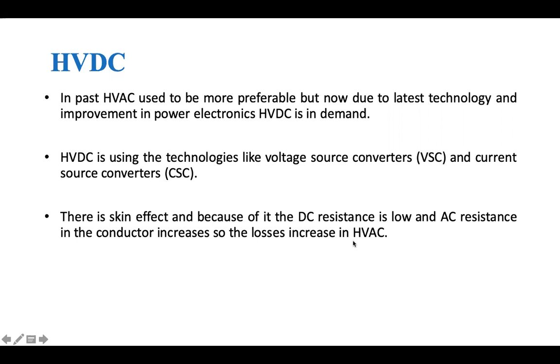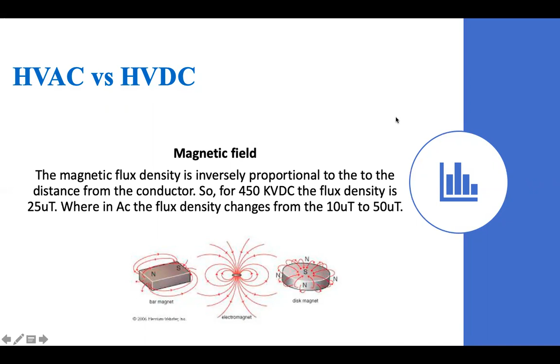Now we will compare HVAC and HVDC with technical parameters like magnetic field. First one is magnetic field. The magnetic flux density is inversely proportional to the distance from the conductor. For the 450 kV DC, the flux density is 25, whereas in the AC, the flux density changes from 10 to 50. So for the same conditions, the flux density is increasing in the AC as compared to the DC.